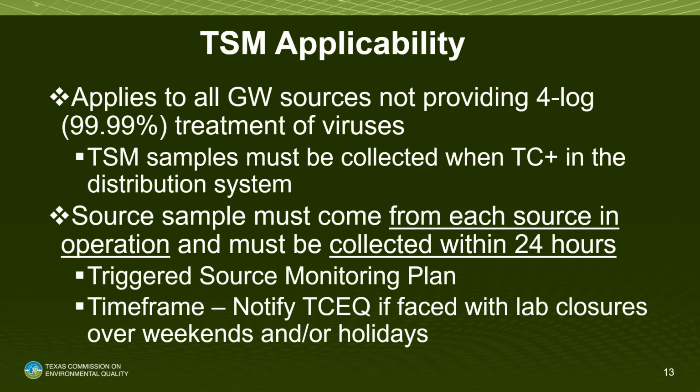There are some systems that are mixed surface water and groundwater, and there's a few out there that will actually route their groundwater through their surface water plant. In that case, that would exempt them from the groundwater rule because it's getting that extra treatment through surface water treatment. But a lot of times those are treated separately, and the groundwater is injected and just sent out to distribution, whereas the surface water will come in and go through the plant.